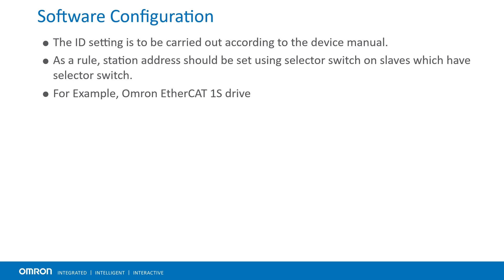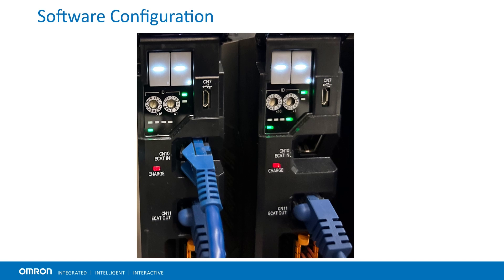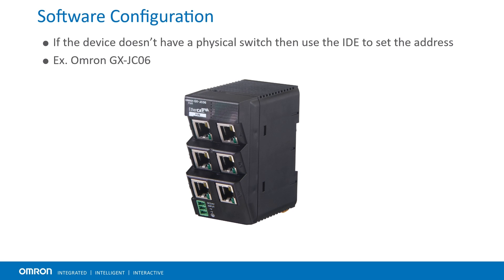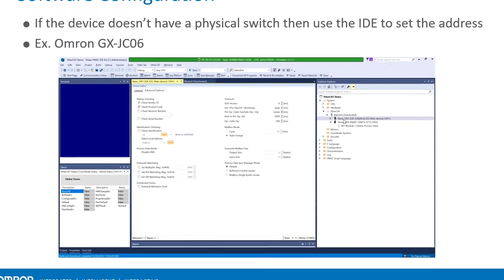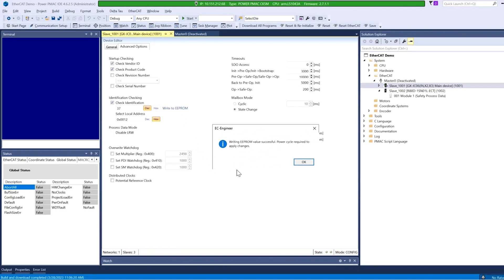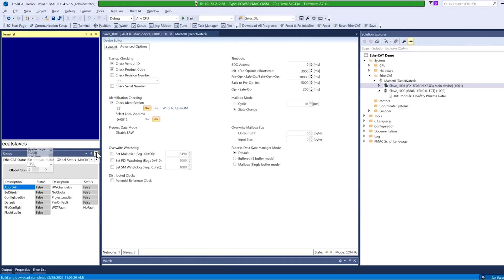Follow the device manual to configure the slave ID. In general, if the EtherCAT devices have a physical switch, it is best to use them for setting up the slave ID — for example, the OMRON 1S drive with rotary switches. If the device doesn't have a physical switch, such as the OMRON JC06 junction slave, then use the IDE to set the address. Enter the desired address under check identification, select write to EEPROM, and restart the device. Issue ECAT slaves to verify the new address.